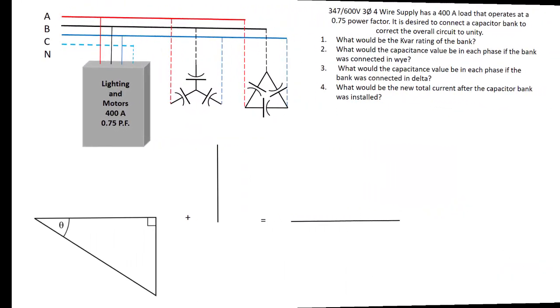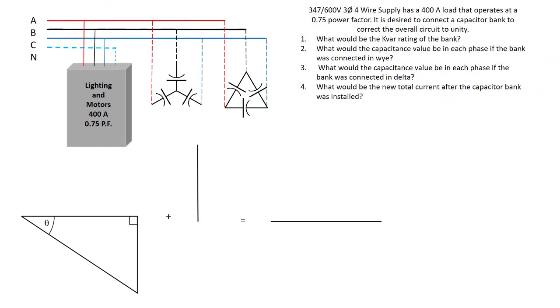We're going to look at a basic power factor correction example. We've got a 347/600V three-phase four-wire supply. It has a 400 amp load that operates at a 0.75 power factor and the question is, it's desired to connect a capacitor bank to correct the overall circuit power factor to unity. Unity basically means that we have no VARs at all coming from the circuit, just true power or in-phase current.